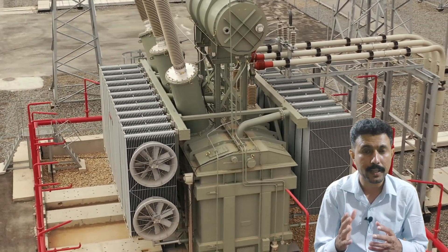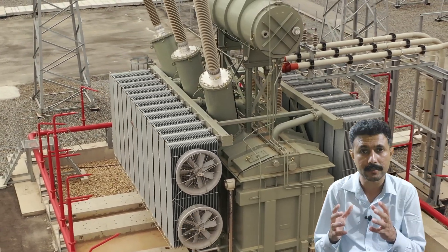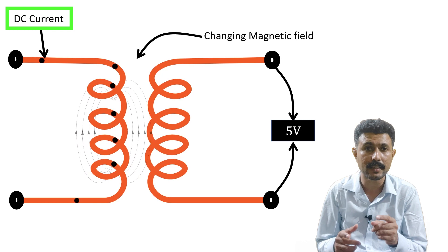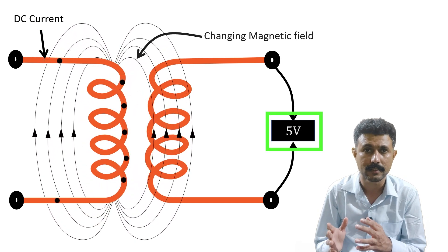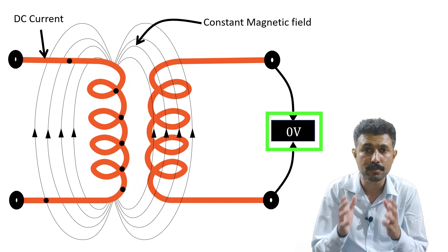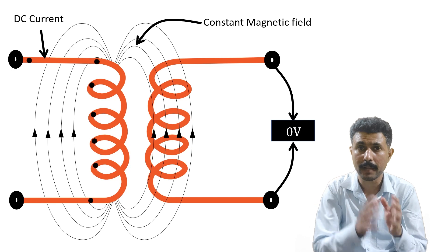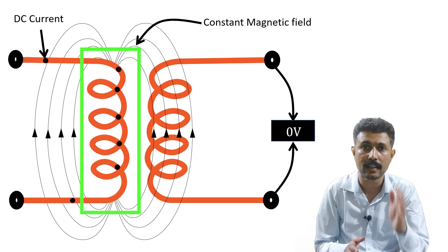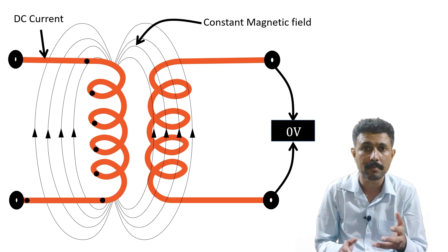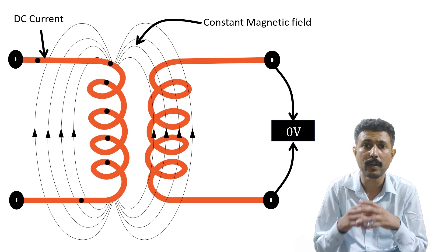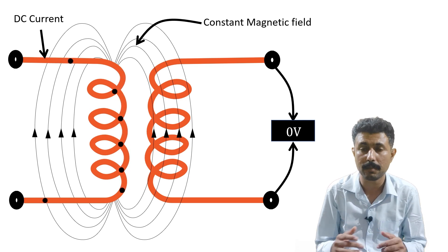When we give DC supply to the transformer, we can observe the following: after starting the DC supply, there is some deflection on the voltmeter on the secondary side, and then that meter goes to zero. So no voltage is shown on the secondary side, while on the primary side a current is still flowing through the primary winding. After some time, the winding heats up and the primary winding will burn.